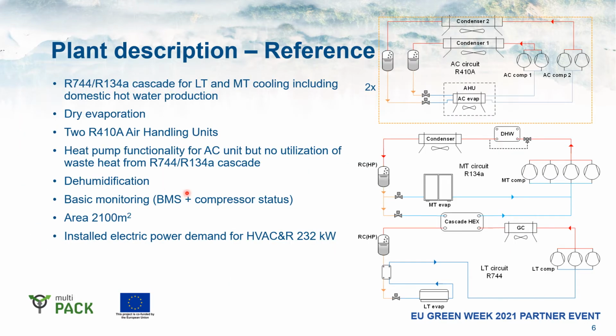If we look at the reference site, it has a bit of a different plant layout. Here we have a CO2 cascade with R134a on the top. So the CO2 system is providing the low temperature cooling for the supermarket, while condensing against the R134a circuit, which in addition provides the medium temperature evaporation level. This system is running solely on dry evaporation, and in addition to this, we have two separate air handling units. These air handling units are running independently of the refrigeration system in the supermarket.